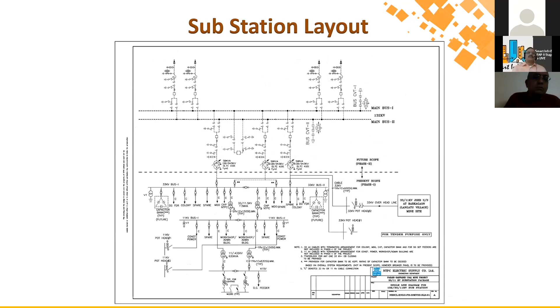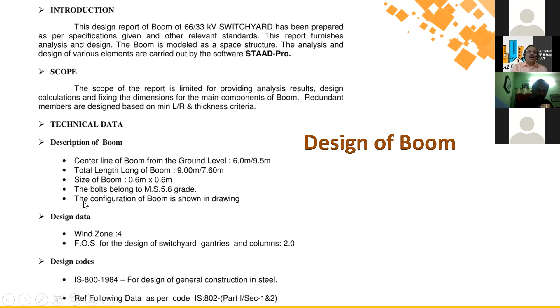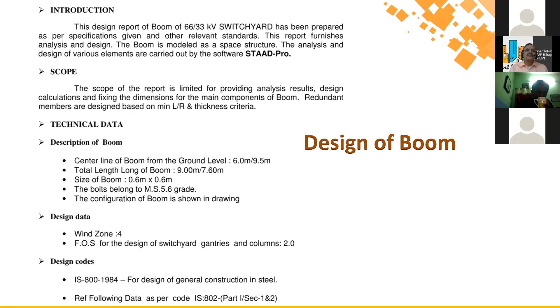We have to consider the wind zone and design codes: IS 800, now it is IS 800:2007, and IS 875, where we have to consider 2015. I'll modify this later. And the steel we use is mild steel or high tensile steel. The configuration of the boom will be shown in the drawing. The boom design is done for shear and bending. It is designed as a simply supported member, and we take WL squared by 8 for the uniformly distributed load of wind and self-weight, and we consider these loading combinations. Short circuit force is taken as the broken condition, and the normal condition is with all conductors intact.